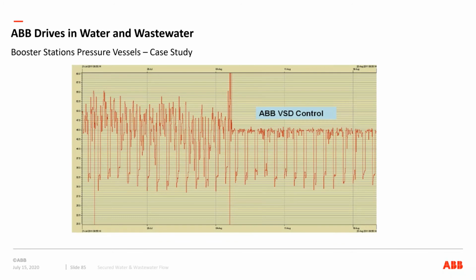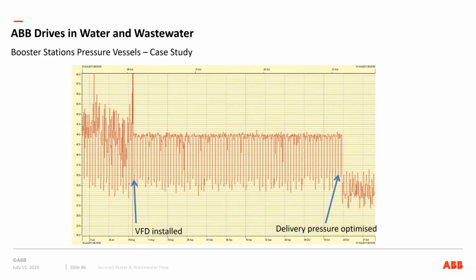If we can go to the next slide, once we do very, very precise control with the delivery system and everything properly done, the VFD saved us energy. We have the wild fluctuations here. And then once we really got the delivery pressure optimized and were maintaining constant pressure, where Mrs. Jones has the water pressure she's anticipating all the time when she turns her water on at a sink, in the shower, for her dishwasher, or at the hose, then she's happy. And that is really where we get some very substantial energy savings, less mechanical wear and tear, less fluctuation in the systems, easier on the pumps, easier on the distribution system, and we have what we really are looking for: a happy customer.